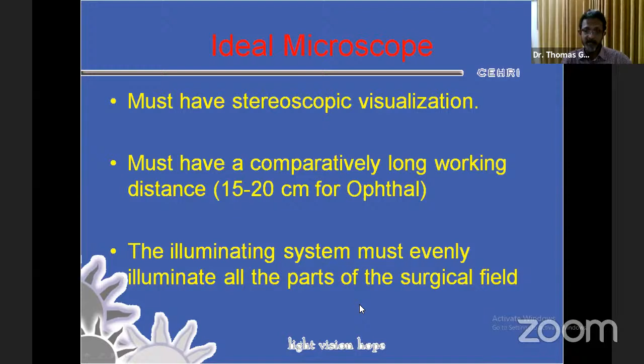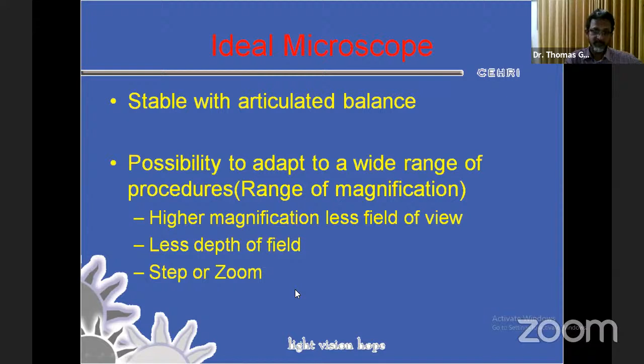The illuminating system must be able to evenly illuminate all parts of the surgical field we are interested in, and that would help not have any shadows and help us in our surgery. The microscope should be stable on an articulated frame and balanced, and one should be able to adapt to a wide range of procedures. That means we need a fairly wide range of magnification. When you go for a higher magnification, your field of view, or the area you see, is going to come down, as also the depth of field, that is your ability to perceive depth and things in focus anteroposteriorly. Obviously, at lower magnification you would see things smaller and your resolution comes down.